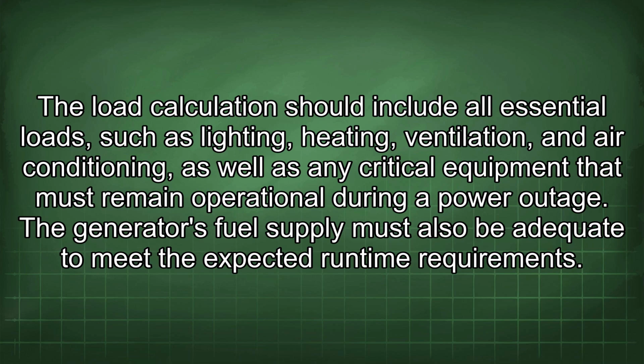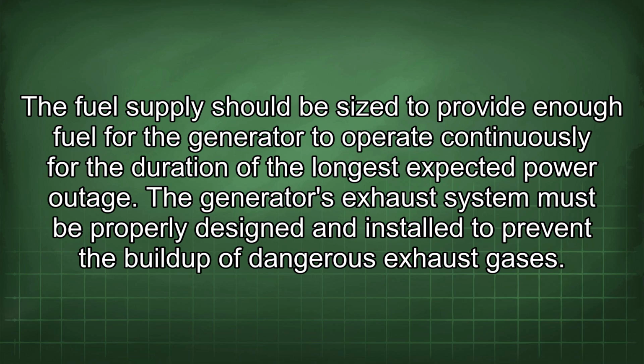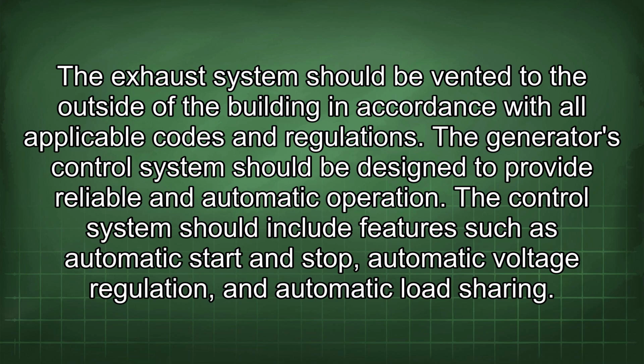The generator's fuel supply must also be adequate to meet the expected runtime requirements. The fuel supply should be sized to provide enough fuel for the generator to operate continuously for the duration of the longest expected power outage. The generator's exhaust system must be properly designed and installed to prevent the buildup of dangerous exhaust gases. The exhaust system should be vented to the outside of the building in accordance with all applicable codes and regulations.